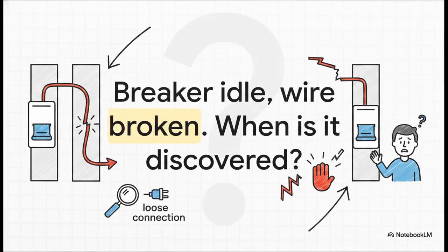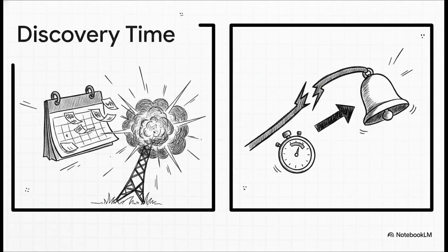Let's do a quick interactive timeline scenario. I want you to really picture this in your head. Say a critical breaker has been sitting closed and idle, perfectly normal for 3 months. Unbeknownst to anyone, the control wire developed a break 2 months ago because of a loose connection. In a system without continuous supervision, when does the operator actually discover this failure? The answer is pretty devastating.